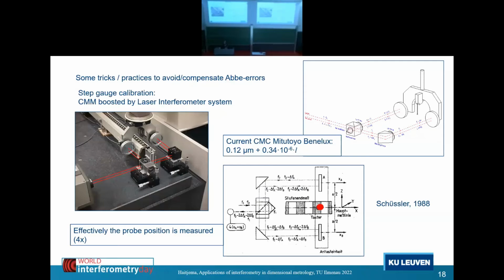Here you see a setup. It's a combination of a CMM and a laser interferometer system which uses here two flat mirrors, and because of these flat mirrors you can move the probe up and down and measure the next one without losing the signal. And the optical scheme is over here, and it comes down to this: you measure this distance 4 times, and in fact you effectively measure the mean of this distance, and that is exactly the position of your probe. So this is a way to compensate also for the Abbe errors in one single interferometer. Okay.